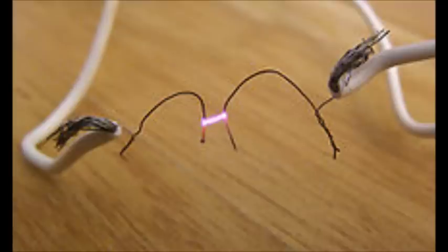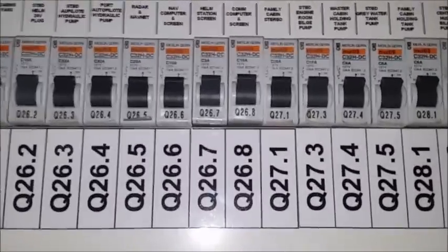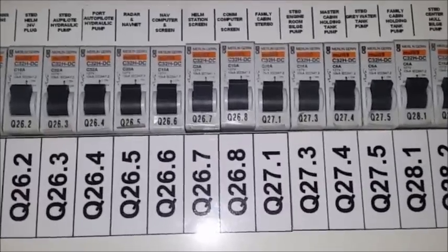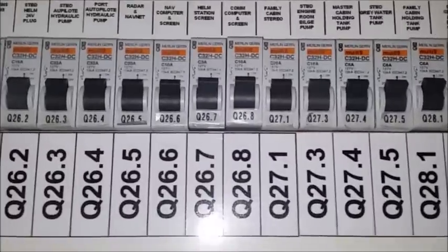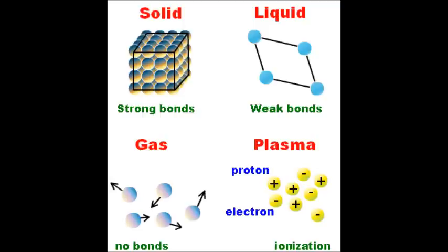That's because an AC is going negative, positive 50 or 60 times a second, depending on if you're in the European or American system. But DC doesn't. The DC breaker stays holding current the whole time that the breaker is trying to disconnect the path. When the breaker tries to disconnect the electrical current path, that arc is super hot — and that super heat makes plasma gas. Plasma gas is the fourth state of matter, and it is conductive. So in effect, the breaker goes to trip, leaves an arc, and as the arc is splitting apart and opening up, it leaves a trail of plasma gas that maintains the arc. Therefore, a DC breaker has to be more robust than an AC breaker.